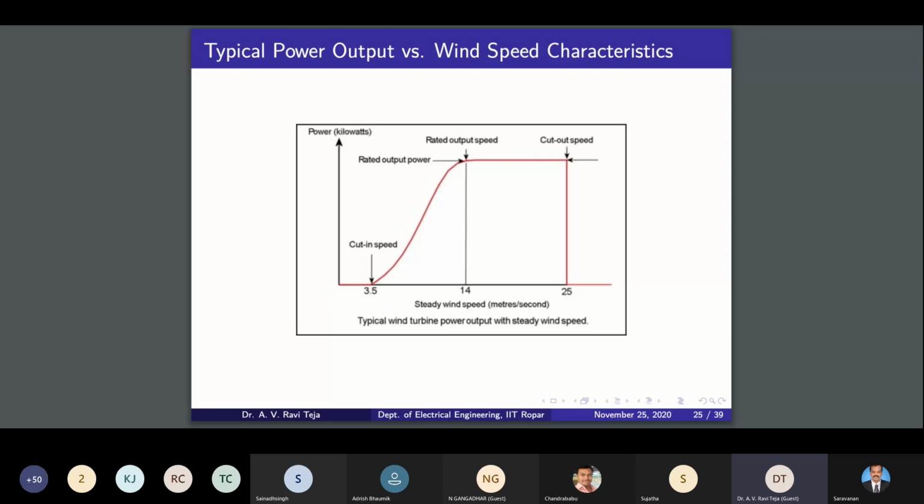Then what I will do is use pitch angle control, but now in an inefficient way. I will align the blades so that the lift force decreases and the power output decreases ultimately. So pitch angle control will take care that power output does not exceed the rated. Because if I exceed the ratings, then more than rated current will flow in the converter as well as the generator. That may spoil the equipment permanently, which I don't want.